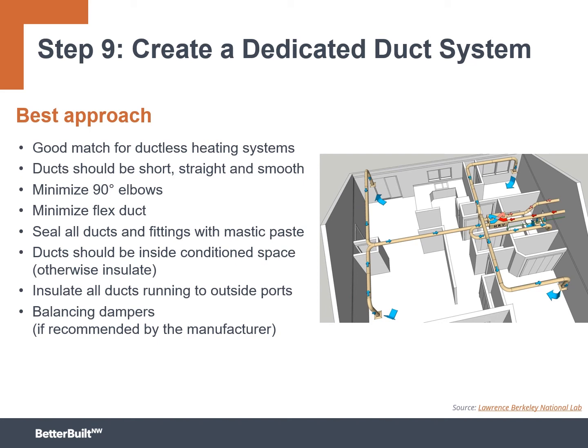And we want to insulate all ducts running to outside ports, and we want to be considerate of the fact we may need balancing dampers if the manufacturer recommends it. This gets to be very interesting, and it's where you want to have really good conversations with your HVAC trade and the distributor, because some brands have balancing dampers built into the heat recovery ventilator, others do not. If it does not, you may need to install them into your ductwork so that you can decide which ones to open a little bit more and shut a little bit more, so you can distribute the air where you need to fairly evenly throughout the home, and pull air where you want to fairly evenly throughout the home.